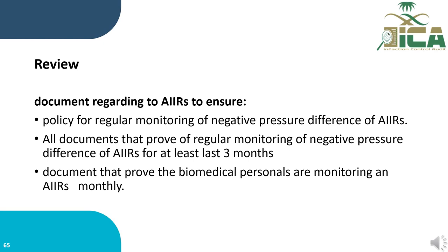You need to review each document regarding airborne infection isolation rooms to ensure that there is a clear policy for regular monitoring of negative pressure difference of airborne infection isolation rooms, and all the documents that prove regular monitoring of negative pressure difference for the airborne infection isolation room for at least the last 3 months. You will review all of the documentation.